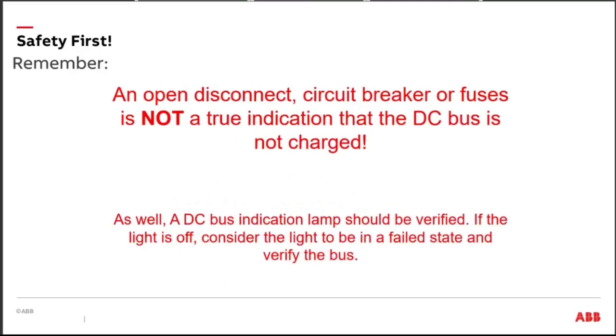With a variable frequency drive, it's hyper critical that you remember that an open circuit breaker or an open disconnect, or pulling the line fuses, does not mean that the DC bus is not 100% charged, even with the disconnects open. If you're looking at a 460 volt main, you're talking about a minimum of 650 volts DC. It will knock you on the ground and you will cry like a broken-hearted schoolgirl. If you ever get your hands on that DC bus, it'll be the worst thing that you ever face, buddy. It's horrible, horrible. On all the drives, ABB, Cutler Hammer, Square D, we're not talking about trade names today. We're talking about drives, okay?